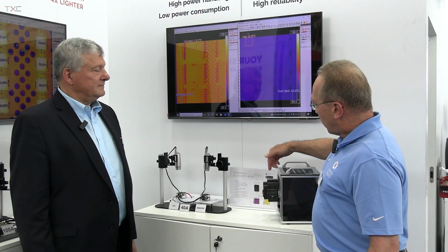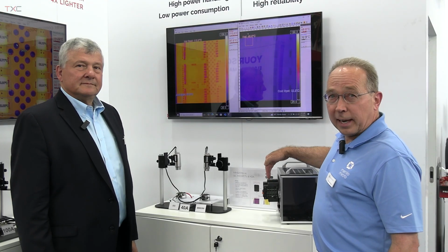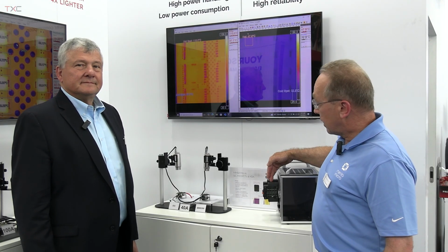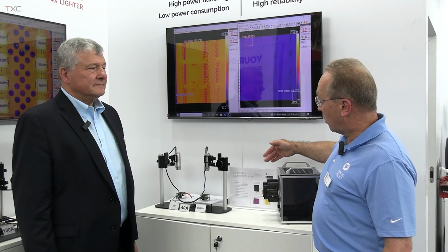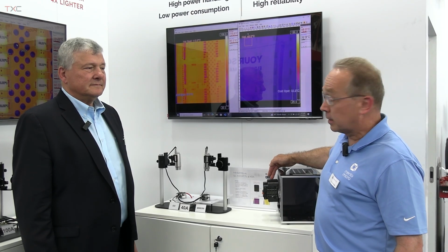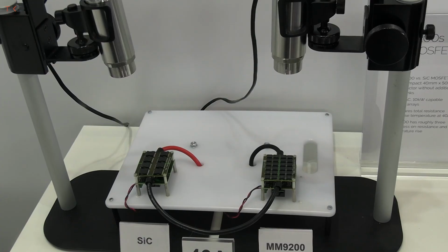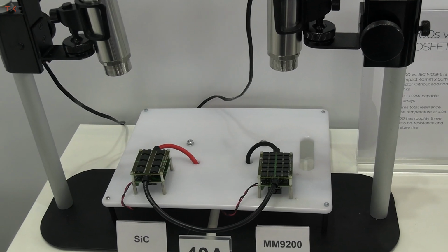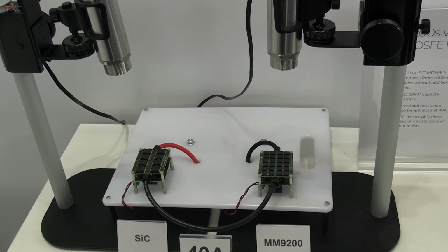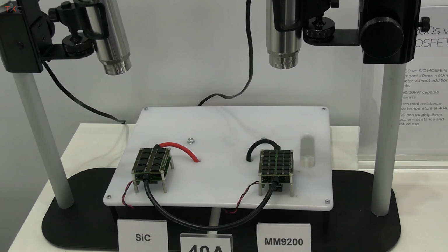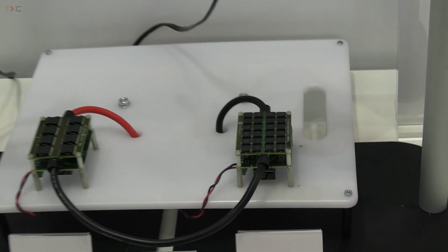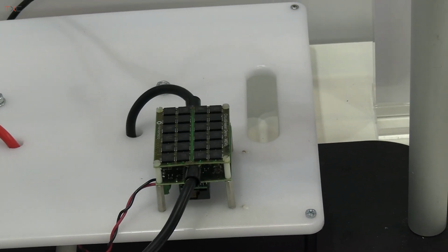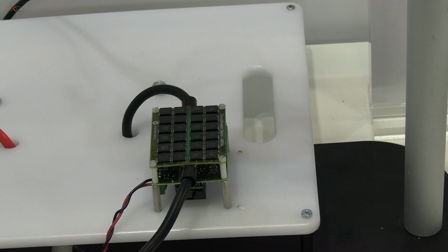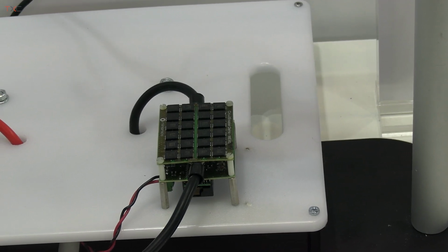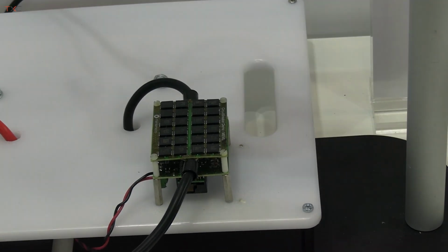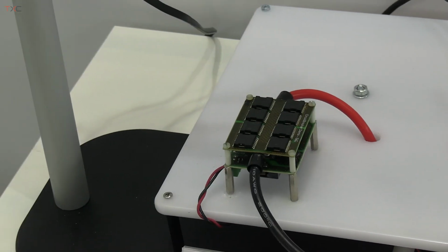So what we have here is the form factor, the number of devices that you could put into a DIN circuit breaker for both silicon carbide and for the MEMS ideal switch. Over here, we're showing those two arrays with 40 amps flowing through them. For the MEMS array, you have an effective resistance of about 1.4 milliohms. And for the silicon carbide array, because of the higher resistance of that technology, the total resistance in that form factor is about 4.2 milliohms.